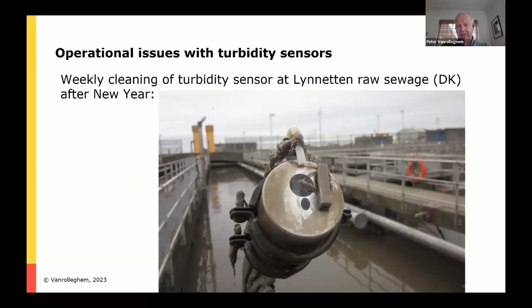Still, we can work with turbidity sensors quite reliably if we choose them well, choose the right type, install them well at the right location in a good corner, and do regular maintenance, and then they keep providing good data. Even in a situation like this, where you think it can't work, it works because you have a compressor that puts air on the sensor tip and keeps the measurement location pretty clean.